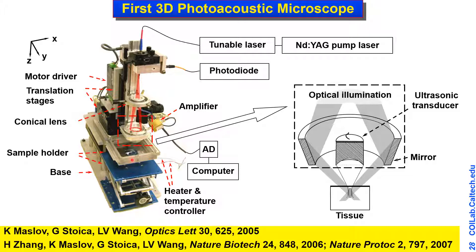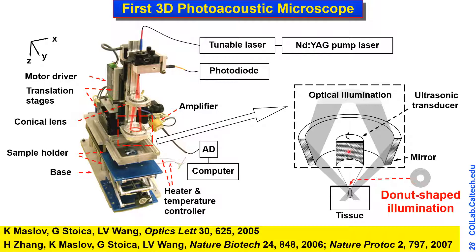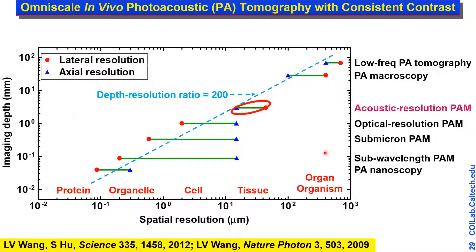The first 3D photoacoustic microscope was built in our lab. The key component uses a donut beam focused into tissue with a dark core on the tissue surface to minimize surface interference. Ultrasound detection is confocal with light illumination to maximize SNR. With a single laser shot we get a 1D image; time of arrival gives depth resolution, and acoustic focusing gives lateral resolution for full 3D resolution. The system head is scanned in a water tray with a membrane window coupling light and sound, giving multiple millimeters penetration at tens of microns resolution.